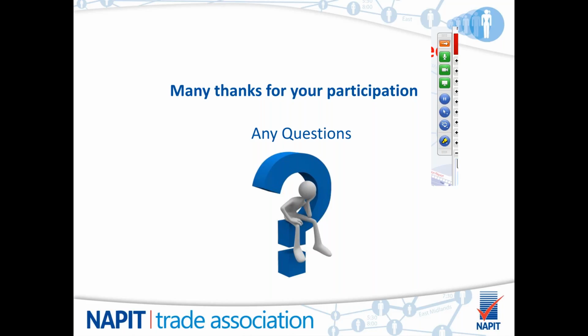Let's say we've come across an installation that isn't being inspected and tested regularly - do we need to do a 100% inspection? Personally, yes, I'd suggest so. You've got no paperwork, no previous documentation or test results to work to. You're turning up with no information whatsoever, so you'll be doing a lot of exploratory work anyway, checking that what's labelled is actually doing what it's supposed to do. Really you'd start with a 100% inspection the first time, and drop it down maybe to a 20% check once you've got documentation to sample to.